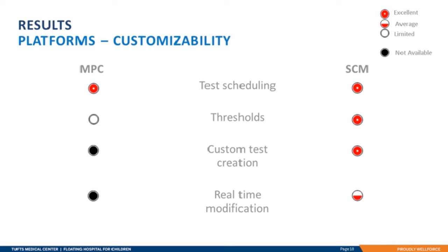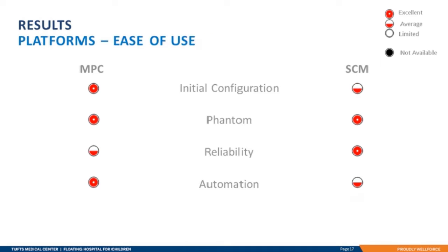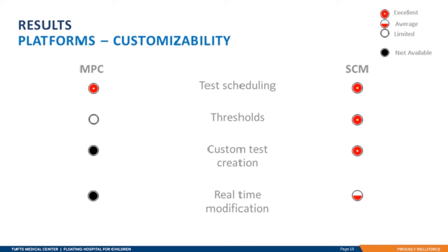available on Monday. Beyond scheduling, however, customizability is where SunCHECK Machine really stands apart from Machine Performance Check in terms of features. SunCHECK Machine is completely customizable to fit whatever your clinic's needs are in terms of daily QA, and also allows for threshold adjustment if you want to have different thresholds than what TG-142 recommends. This might happen if you have a desire to have tighter tolerances. Machine Performance Check does have thresholds, but they are not changeable, nor are any of the tests. What you see is what you get.